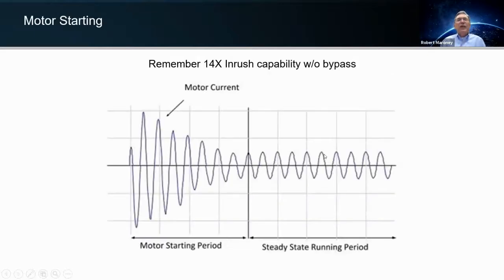Well, it's a similar answer to the one we just talked about for the MRI. When you take a look at a motor load, you have starting. Now, if you're on a VFD, you only have 2 to 3 times nominal current for starting. But sometimes you need to handle a motor across the line, which, as we all know, depending upon the rating, can be as much as 7 times nominal current.